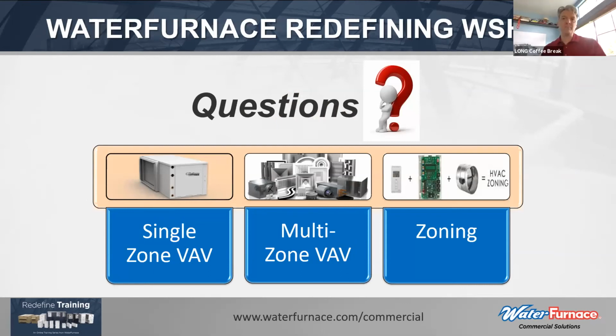Rich. Again, if you have any particular questions, please type them into the chat area and we'll get to them as they come about. A few thoughts or ideas. Right sizing is so important, especially when it comes to water source heat pumps. Unfortunately, while you do have a variety of sizes, you may not be able to hit your load exactly. And I know as engineers, it's extremely challenging to find out and forecast what that load is going to be, given the changing nature of projects and construction and how that impacts sizing. But one of the benefits of this technology that I certainly want to point out is that you do have the ability to have that diversity for the entire system that you're serving. You have a greater swath that is served by one single unit.